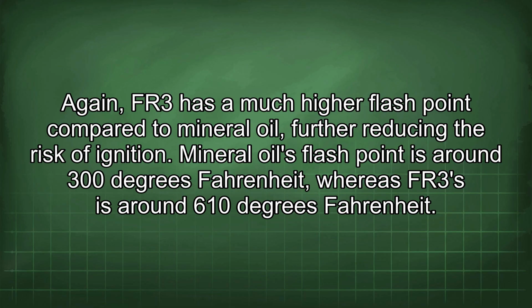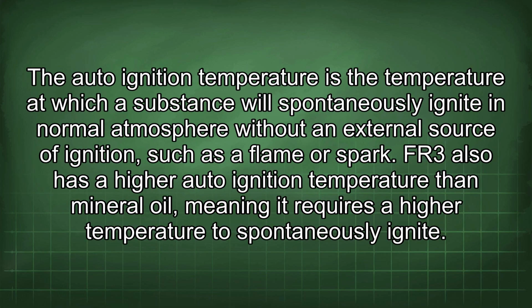Again, FR3 has a much higher flash point compared to mineral oil, further reducing the risk of ignition. Mineral oil's flash point is around 300 degrees Fahrenheit, whereas FR3's is around 610 degrees Fahrenheit. The auto-ignition temperature is the temperature at which a substance will spontaneously ignite in normal atmosphere without an external source of ignition, such as a flame or spark. FR3 also has a higher auto-ignition temperature than mineral oil, meaning it requires a higher temperature to spontaneously ignite.